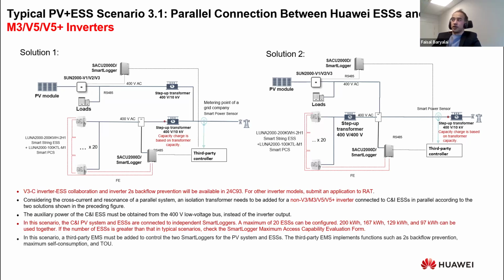But it's also important, for instance, if the grid collapses and we still want to run the energy storage to provide energy to our industry—since the inverter, the PCS, is asymmetrical power, the load might be unbalanced. So the isolation transformer is also important for that reason.